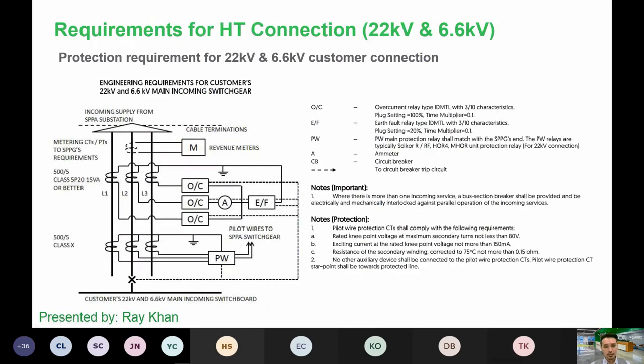Okay, so this slide covers a bit more. This slide talks about the connection requirement for 22 kV, also a 6.6 kV connection. So on the bottom left in here, we see there are pilot wire connections. So you can see it's 500/5. In some of the designs that we see in the market, some of the designers put 500/300/5. With this latest revision, there's no more 300 in here. So it's just purely 500/5.